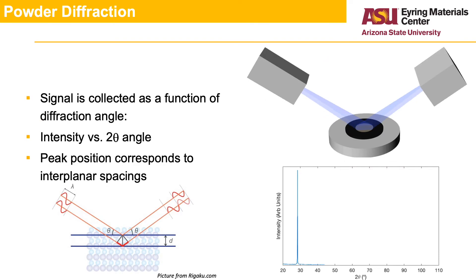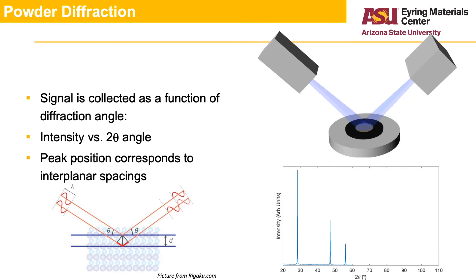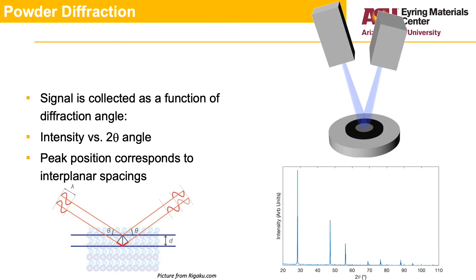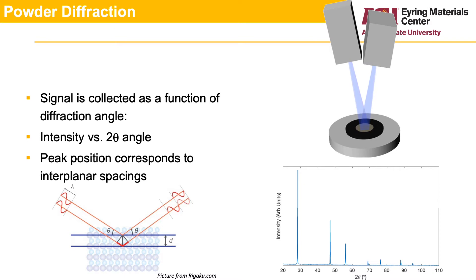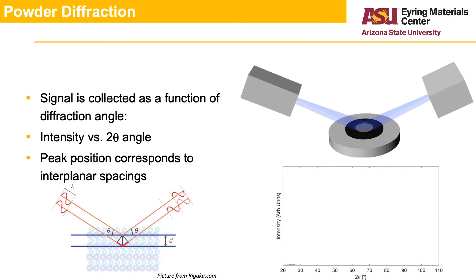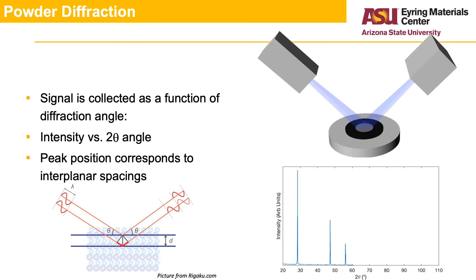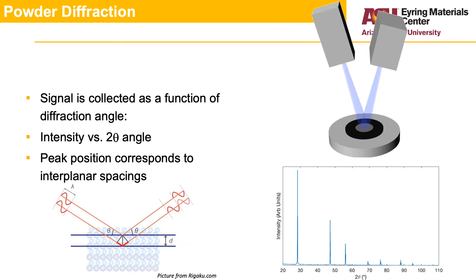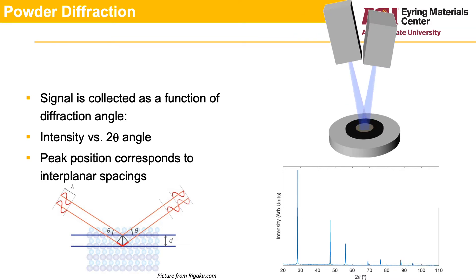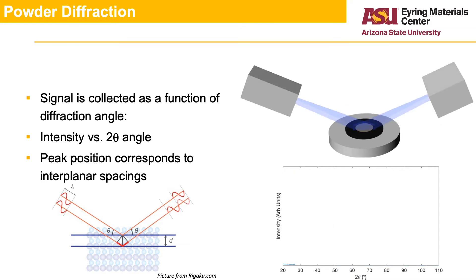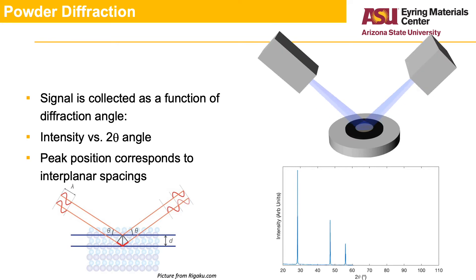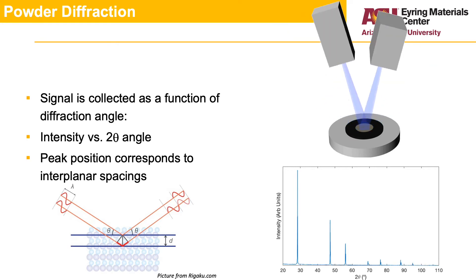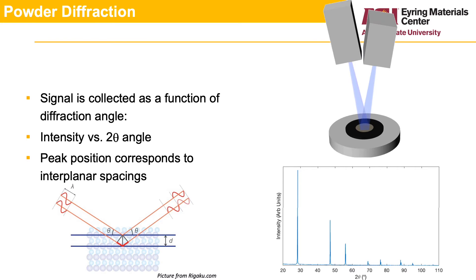In a powder diffraction experiment, the signal is collected as a function of 2-theta angle, while the sample is illuminated with nominally monochromatic X-rays. The peaks observed correspond to specific d-spacings from specific crystal orientations. The plot of intensity as a function of 2-theta can then be used to determine the material present and the lattice and structure of the material.